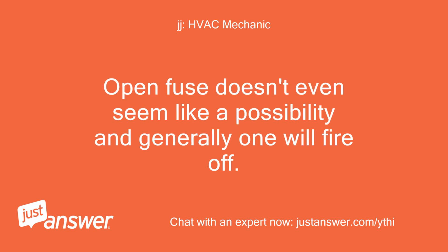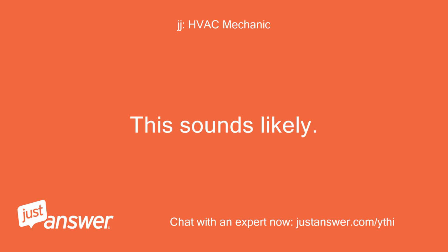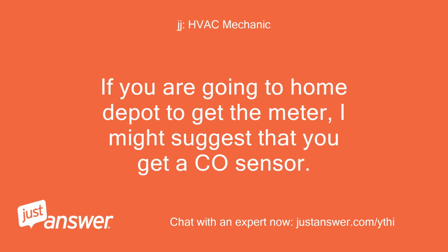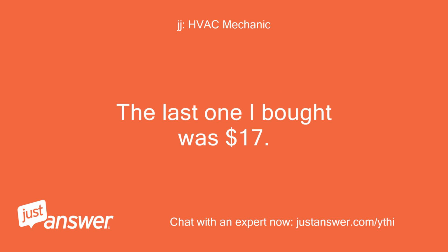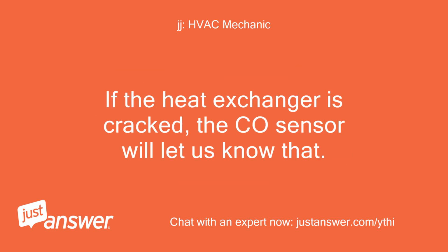Open fuse doesn't even seem like a possibility, and generally one will fire off. Sometimes those ROLLOUT switches will fail from repeated resets. This sounds likely. We may have to address what is causing the ROLLOUT to trip. If you are going to Home Depot to get the meter, I might suggest that you get a CO sensor. They are very inexpensive nowadays and every old furnace should have one. The last one I bought was $17. That reset switch has been trying to let you know that the combustion system is not exhausting properly. If the heat exchanger is cracked, the CO sensor will let us know that.